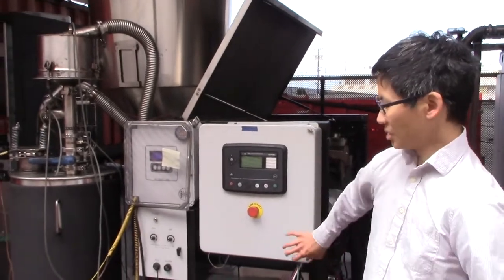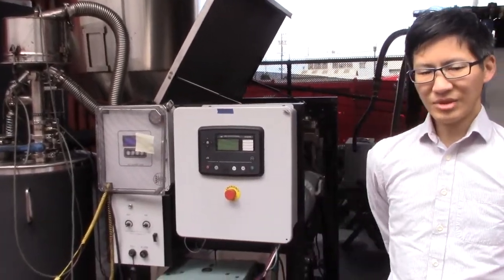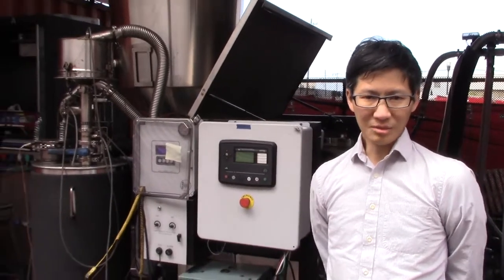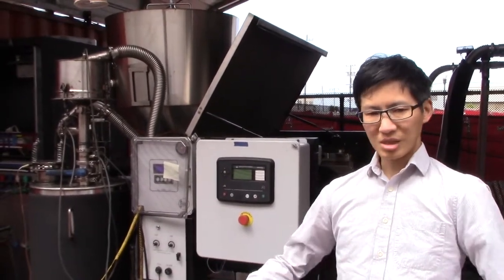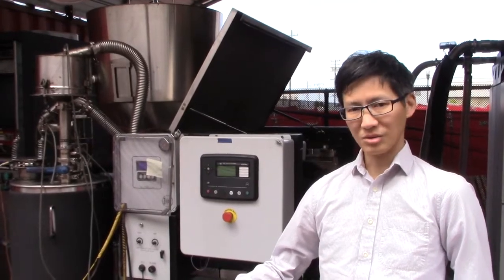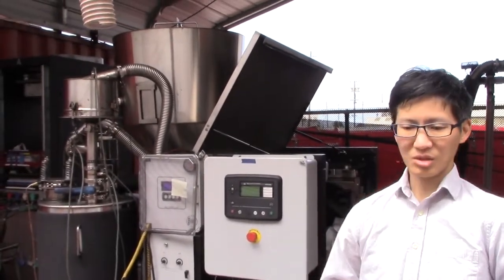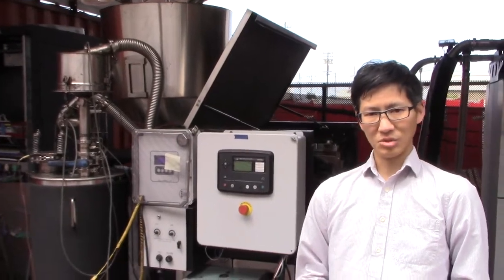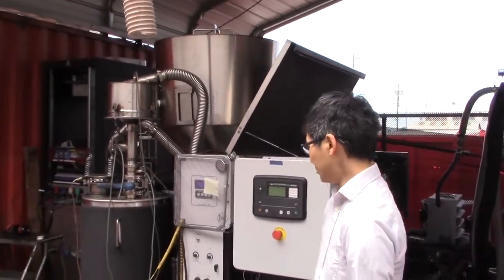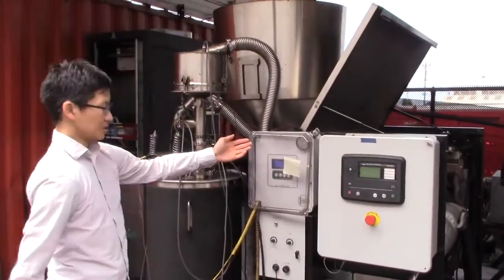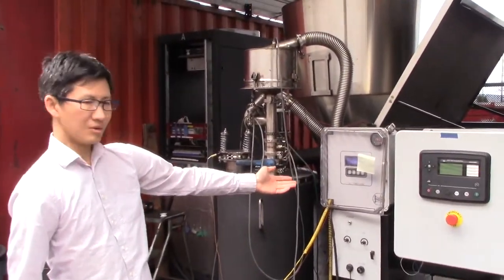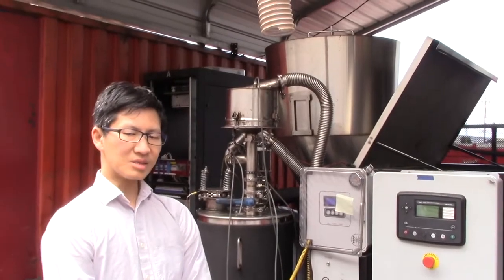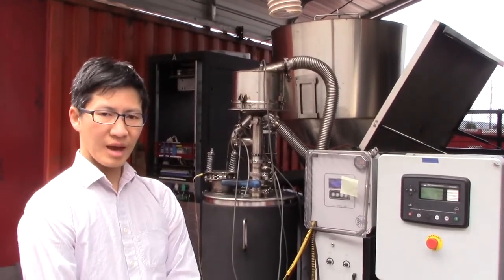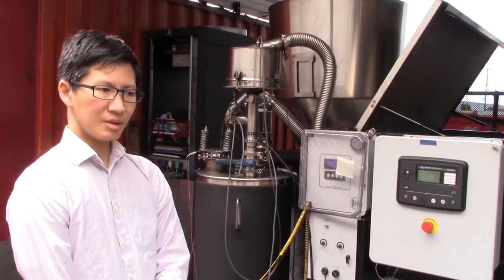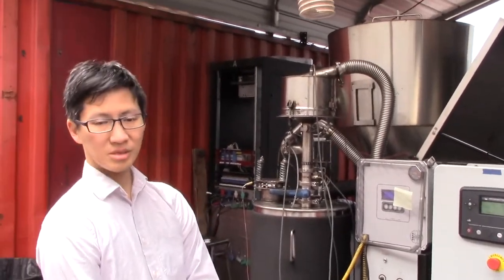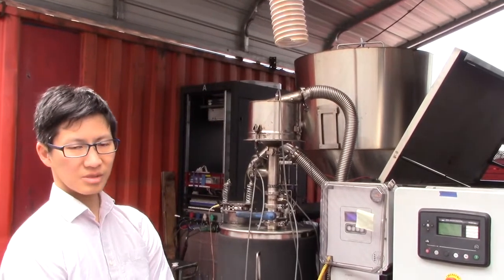Well, the grid tie controller is actually fairly desirable, even if you don't connect the machine to the grid, because the grid tie controller enables you to synchronize multiple Power Pallets into a microgrid, or to synchronize this with any other existing microgrid that may have small-scale wind or solar on it. Right. So over here, this device over here is the PCU, and it carries out the monitoring of the gasifier. It reads the temperatures and the various pressures in the different zones, and if there are any alarm conditions, the PCU is the system that actually sounds the alarm.